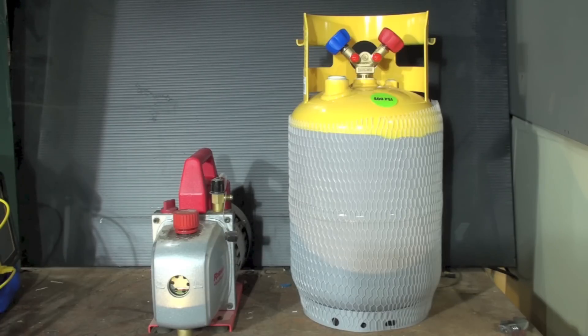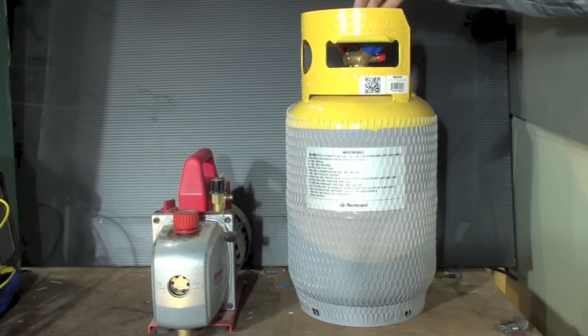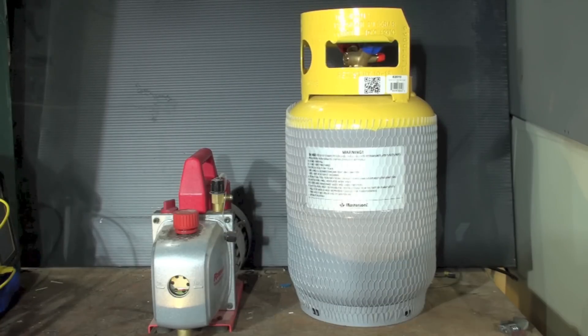So anyway, let's go over a few things about these cylinders. They're obviously a reusable cylinder. A lot of guys say, well, I'll just take a throwaway cylinder and use it. If the throwaway cylinder was made since about 1990, you can't do it because the check valve in it—you can only take pressure out. They're really not a great idea anyway. They are throwaway for a reason. These things have to be tested every five years. Your test dates are on the side here.